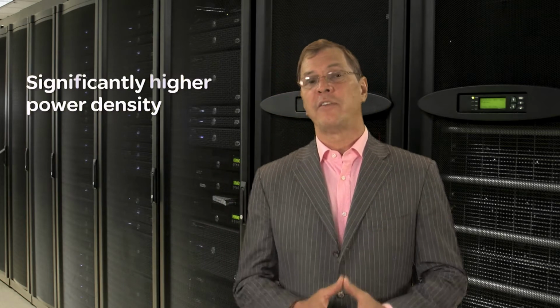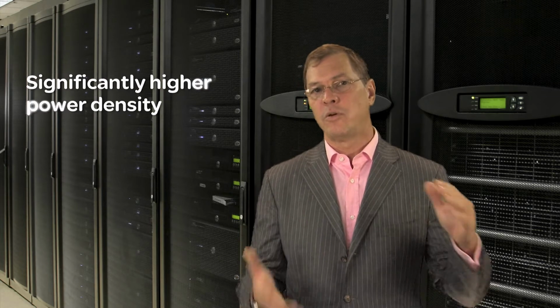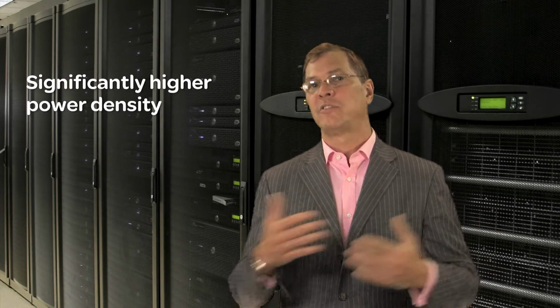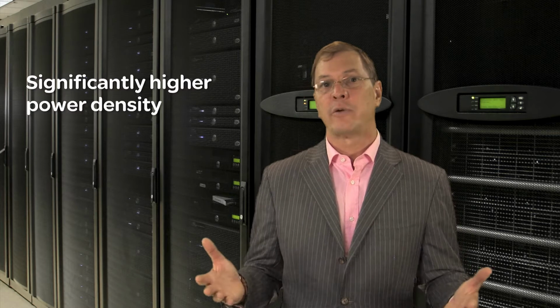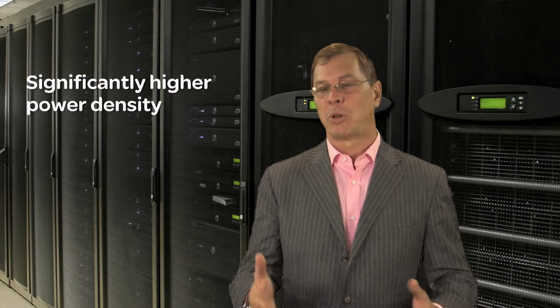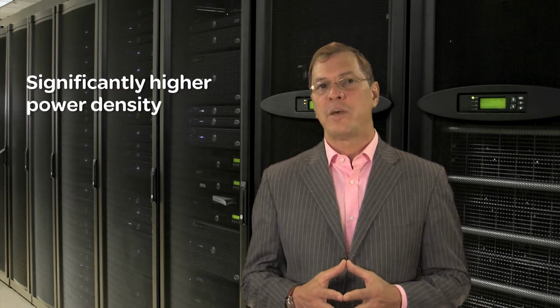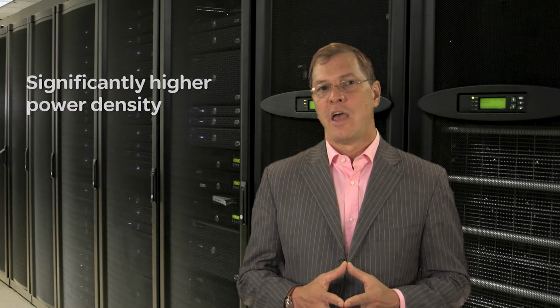Another attribute that comes along with cloud is generally a significant higher density. Because of the uniformity of the IT equipment and the absence of a lot of other ancillary type IT equipment devices or blank space in cabinets, we typically end up with higher densities. And generally 8 kilowatts a cabinet is about the minimum kind of density we will see in a cloud environment, but it could be up to 25 or 30 kilowatts per cabinet in a cloud environment.